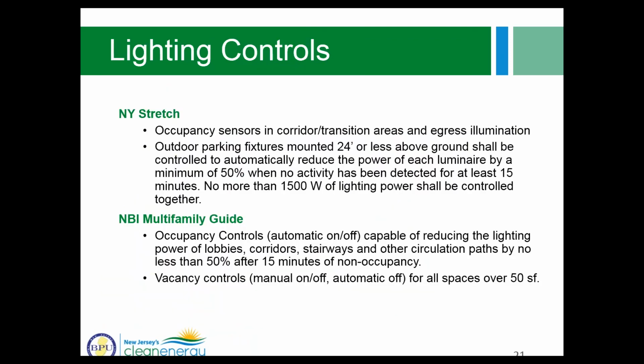So lighting control requirements are very stringent already in 90.1 2016. So daylighting is expected in and must be specified in most spaces with windows, except residential spaces such as apartments, hotel, motel, guest rooms. There should be lighting controls specified in corridors, and there were some questions concerning the spaces before, because some projects thought that it's unsafe to have occupancy sensors there. But again, now that's part of the code requirements, and it's also a requirement of New York stretch.